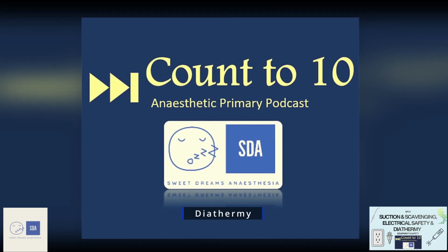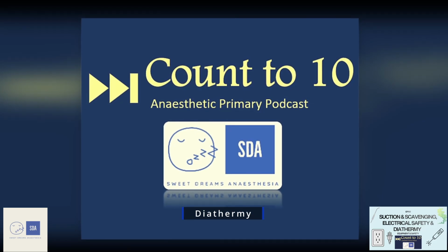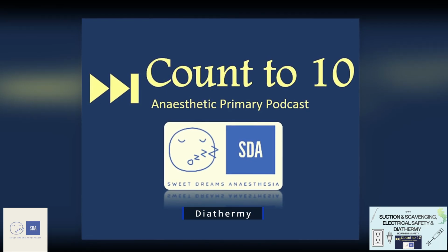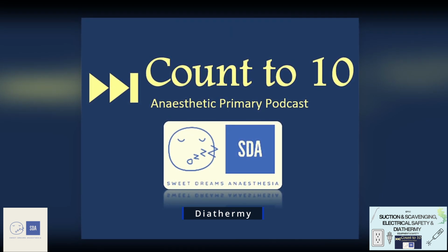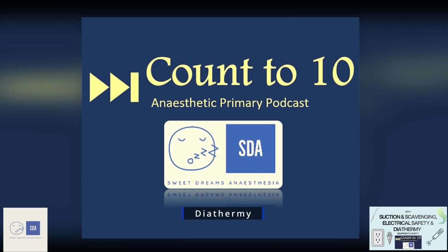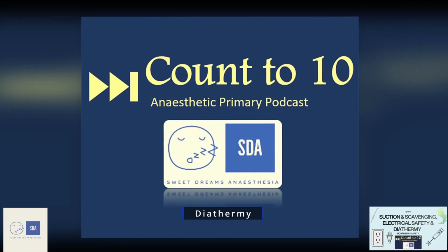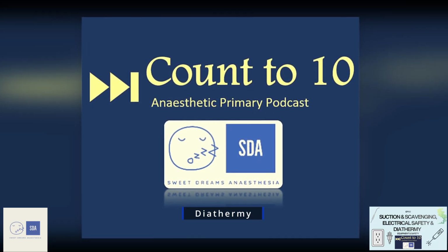For VF to occur with diathermy, its frequency needs to be dropped down to ideally 50 Hz, because this is the frequency where you can really cause big damage to the heart. Now, the other problem with diathermy is that it's still a risk of causing burns to patients. It's electrical equipment that's exposed to patients. What we get specifically worried about is high current density, specifically at that ground plate. If that ground plate isn't adhered right to the patient, then all of a sudden you're increasing the current density, and this can be a huge risk for a localized burn. Thankfully nowadays, the diathermy device usually won't work or will come up with a pop-up message saying attach ground plate if it's not adhered right.